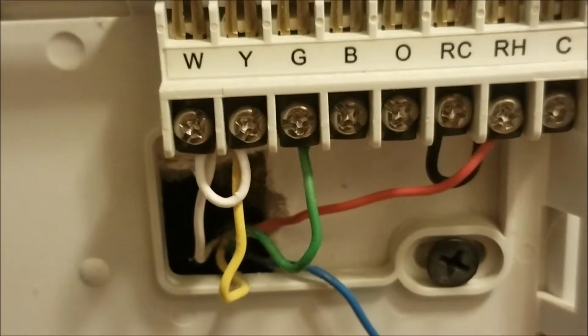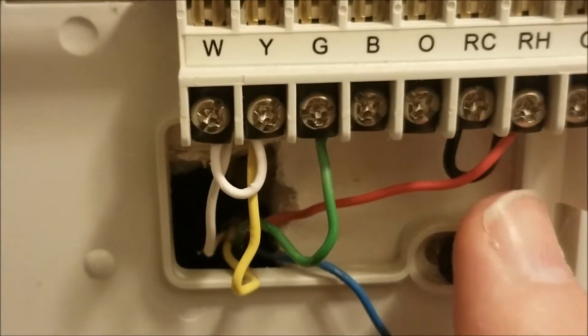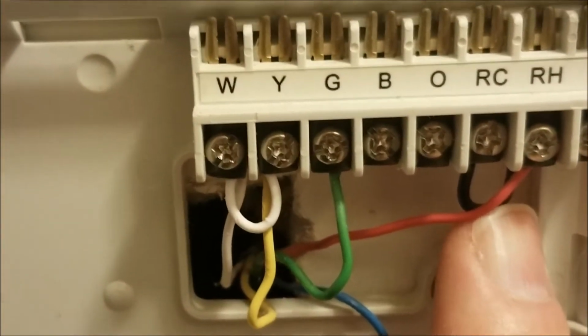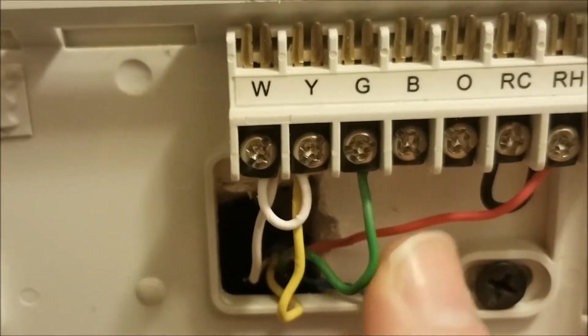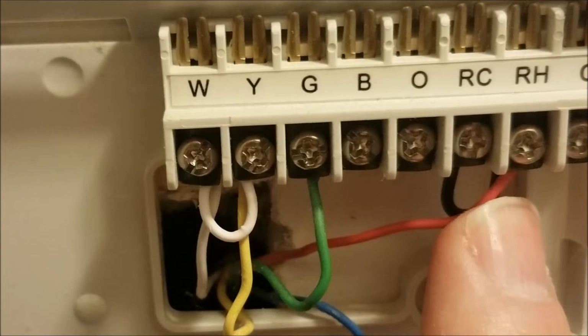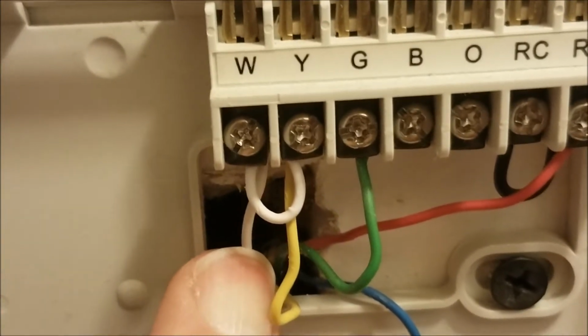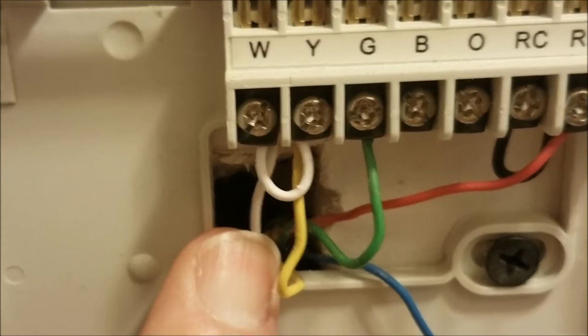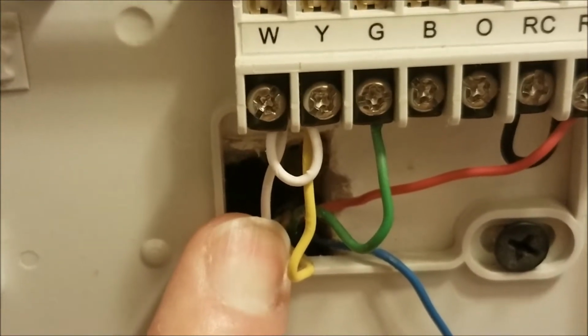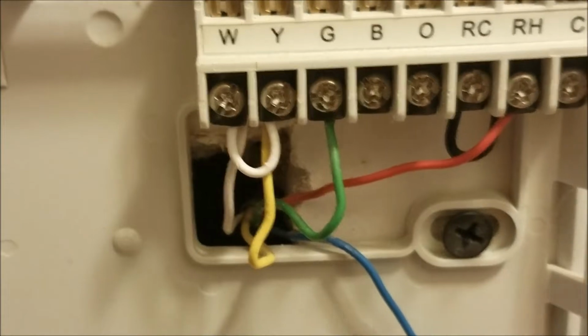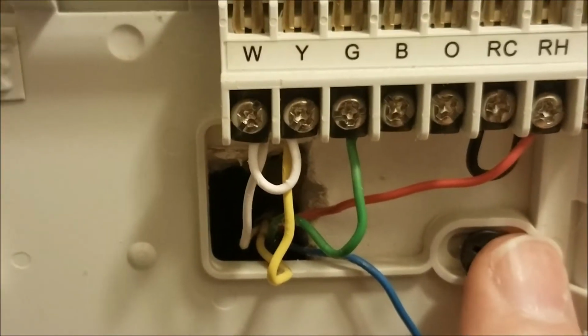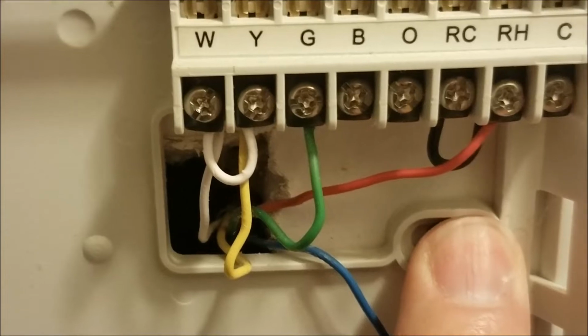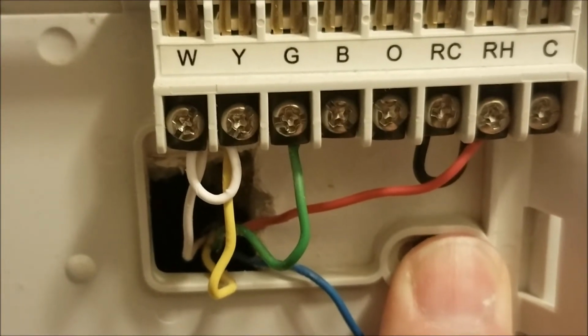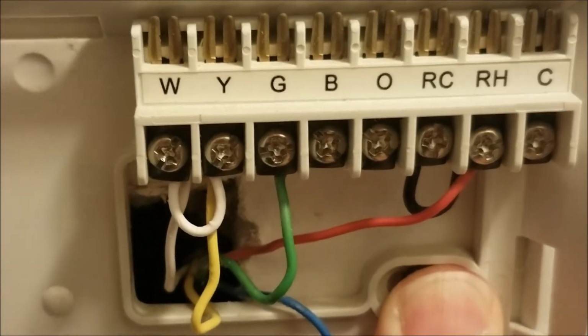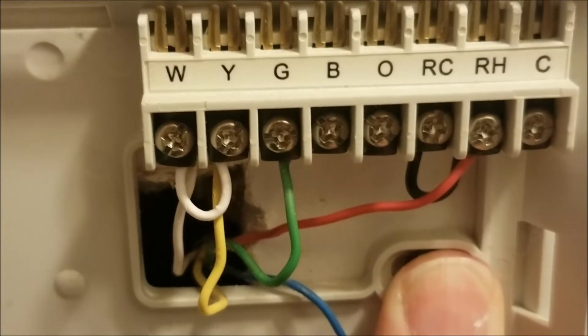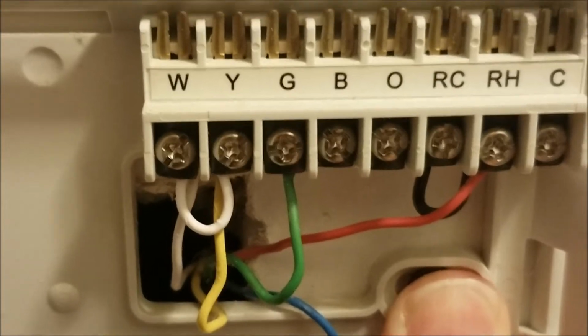In my system, I had a gas system, so this red wire, when I'm in heating mode, will turn on the fan and also send voltage through that same relay to this white wire. So that tells the control board on the furnace you're in heating mode, turn on the gas. The heat pump's a little bit different. The heat pump has to know also what mode it's in, but it shares a compressor. So the compressor in one state works as cooling, meaning it takes the heat out of the building. In the other state, it works as heating. It takes the heat out of the air and puts it into the building.